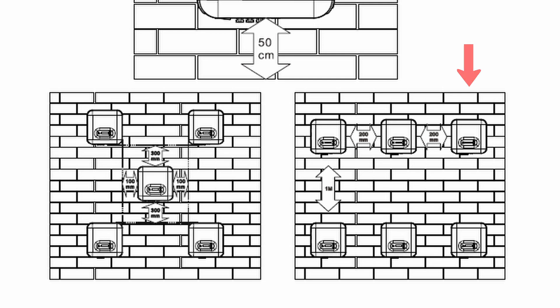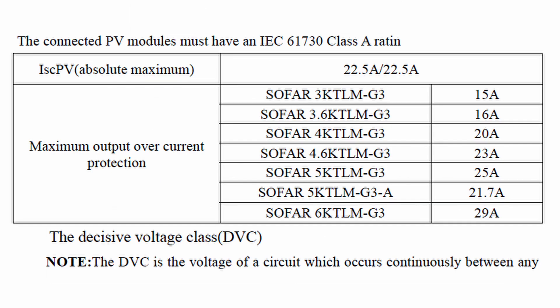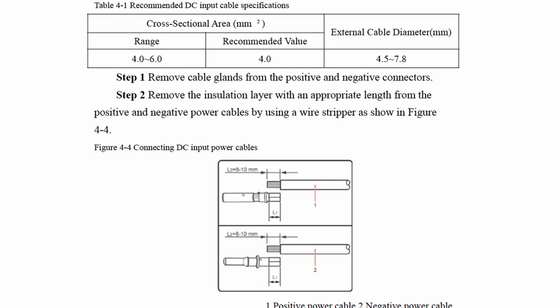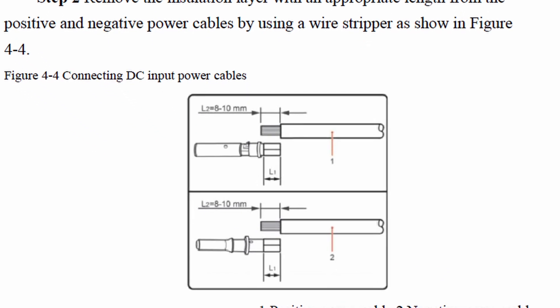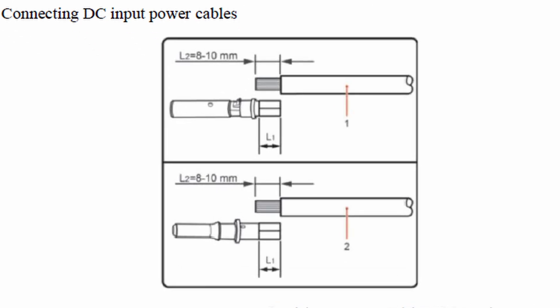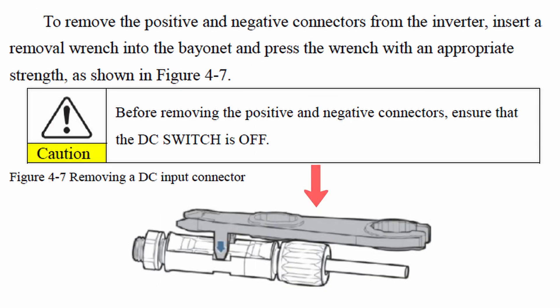For electrical connections, based on the current you can choose the wire sizes. Connecting the DC input power cables should range between 4 and 6 square millimeters - recommended is 4. External cable diameter is 4.5 to 7.8 millimeters. Make sure you strip the wire to connect the MC4 insert corresponding to the diagram. If you strip more, that can cause a short. Use appropriate tools for removing the MC4s.